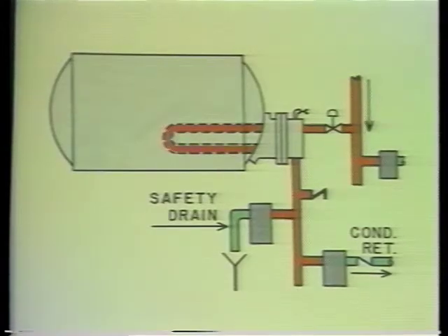These heat exchangers frequently are supplied with low-pressure steam or have control systems which modulate to very low pressures, as is normally the case with storage water heaters. This creates drainage problems similar to those that we discussed in relation to air coils, having the same steam supply conditions. Since the F&T trap is particularly suited to the handling of large volumes of air and condensate at low pressures, it is again recommended.